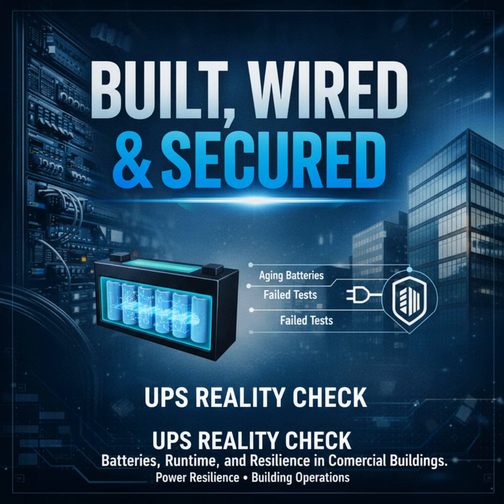Distributed UPS, deployed at door controllers, comm closets, or critical racks, reduces single-point failure exposure and often aligns runtime more closely with what each system actually needs. The trade-off is cost and maintenance complexity, more units to monitor and service. You decide based on criticality and tenancy. Ask, are we protecting a whole floor's meeting rooms or a few racks that host emergency services? That answer directs whether centralized savings are worth the operational risk.